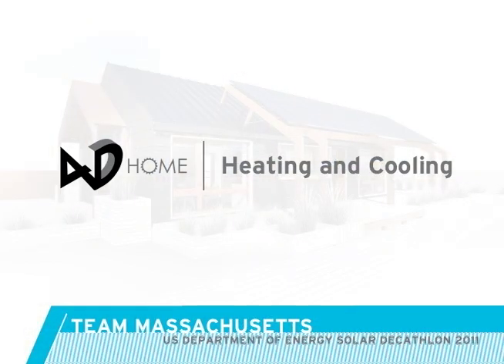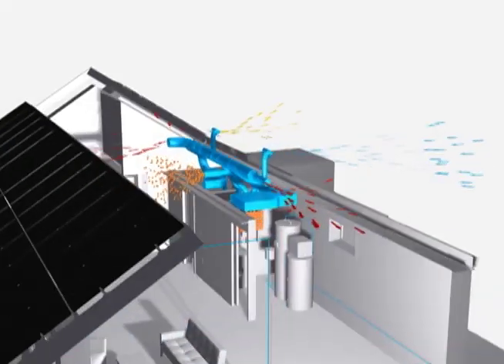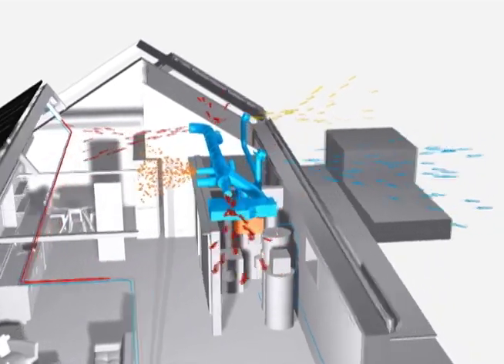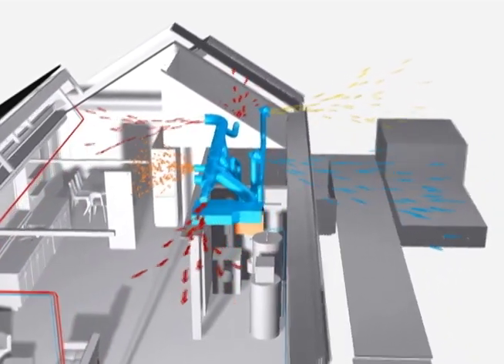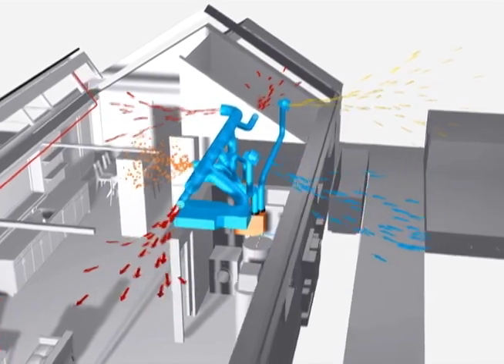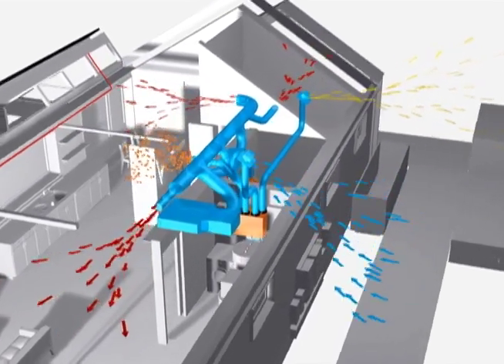The 4D home is heated and cooled by a highly efficient heat pump. In this split heat pump, a refrigerant is pumped between an outdoor unit and an indoor unit. The fluid can absorb heat from the interior air and transfer it outside, which cools the home, or it can absorb heat from the outside air and transfer it inside, which heats the home. Unlike conventional electric heaters that use electricity to create heat inside the house, a heat pump uses electricity simply to transfer heat, making it much more efficient.